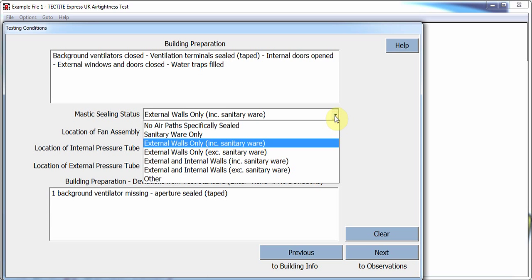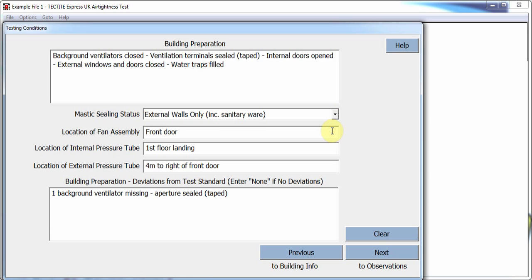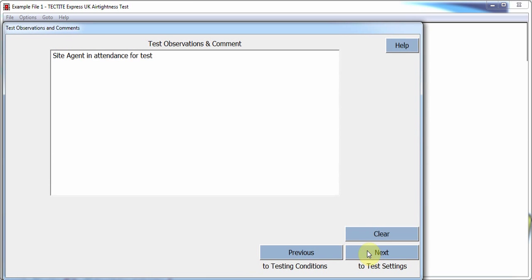It is a requirement of the ATTMA Competent Person Scheme to record the mastic sealing status within the building; the most appropriate option should be selected from the drop-down list. It is also a requirement to record the location of the fan assembly and the location of the internal and external pressure tubes in the fields provided. The test observation and comment field allows the user to record any further relevant information; it is not reproduced in any reports or exports.